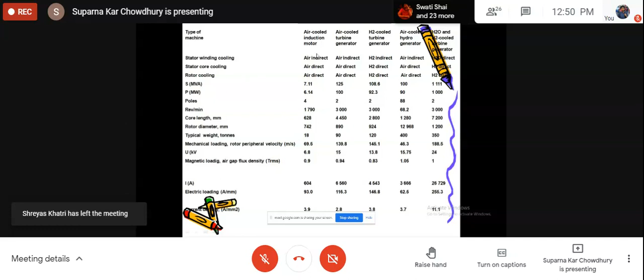Now stator core cooling, again depending on the machine: air cooled induction motors, it is direct air cooled. Air cooled turbine generator is direct air cooled. Hydrogen cooled turbine generator, it is hydrogen direct. Air cooled hydro generator, air direct. And for this turbine generator, this is hydrogen direct. Now, you can see that the winding cooling is indirect. That is obvious because the winding is inside the slots. So the core will be in touch with the cooler directly, not the winding.